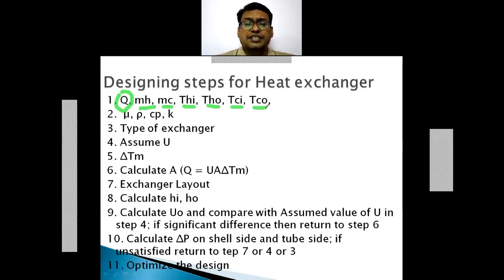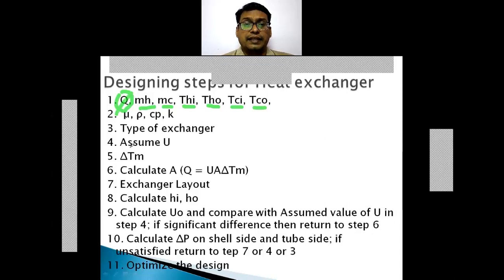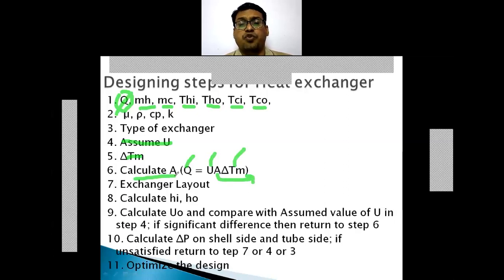The next step is to calculate the mean temperature difference — the log mean temperature difference — and apply a correction factor to get the corrected mean temperature difference ΔT_m. Then calculate the required heat transfer area. Since Q was calculated in step one, and we assumed U and calculated ΔT_m, the required area A can now be determined from Q = U × A × ΔT_m.